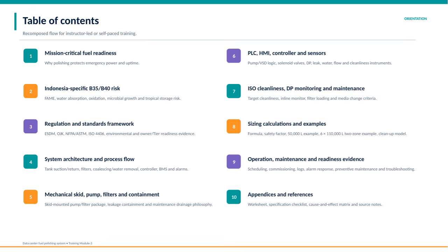We'll also delve into the programmable logic controller, PLC, human-machine interface, HMI, controllers, and sensors, covering the logic behind pump variable speed drives, solenoid valves, differential pressure monitoring, leak detection, water and flow measurements, and cleanliness instruments. Further, the training addresses ISO cleanliness standards, differential pressure monitoring, and maintenance practices, including target cleanliness levels, inline monitoring, filter loading, and criteria for changing filter media. We then move into sizing calculations with practical examples. This covers formulas and safety factors, including a 50,000-liter example, a two-zone example with 6 by 110,000 liters, and a cleanup model for real-world application.